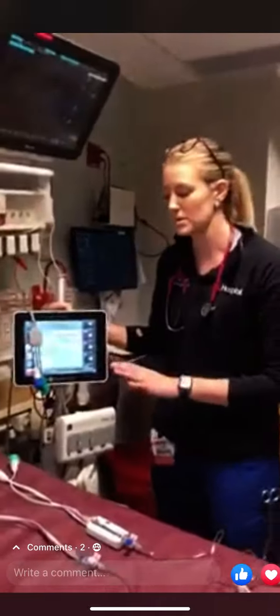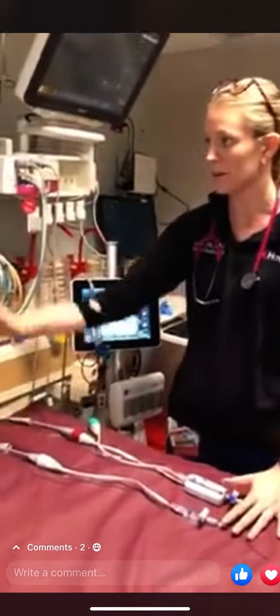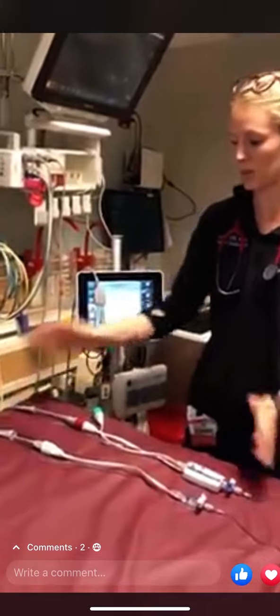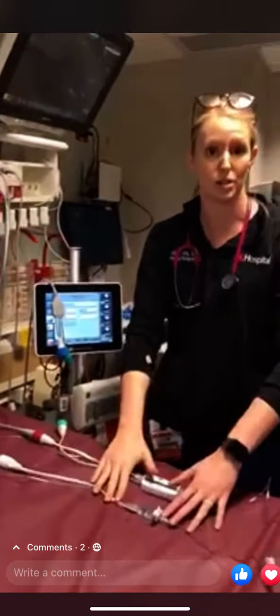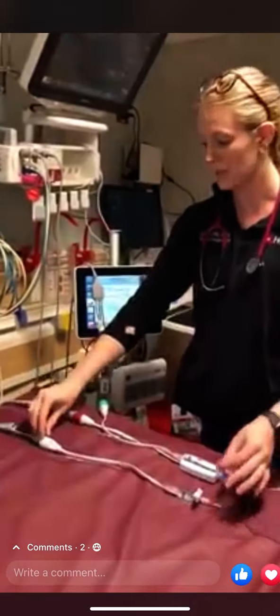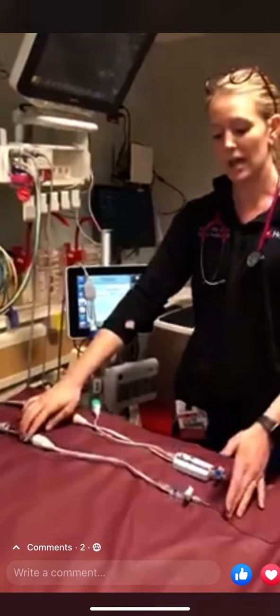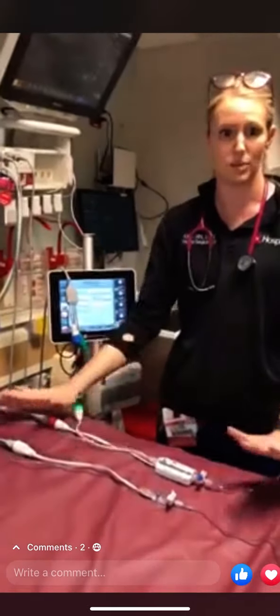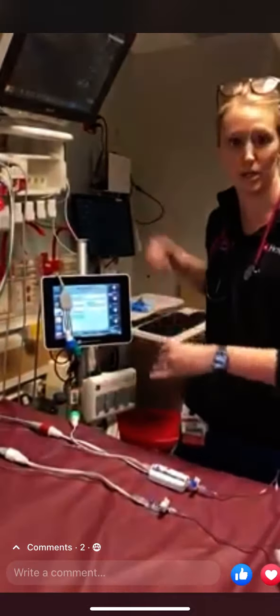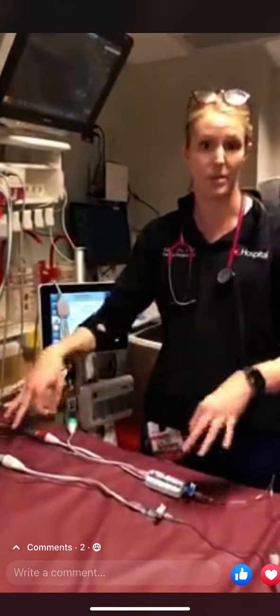Then once you've got both your cables already set up and plugged in, you're going to go ahead and start to connect your EV1000 to your cables. So I already have this set up here. We have our A-line hooked up to a pressure cable and to our monitor, and we can say hypothetically for this scenario our patient was already being monitored and has a CVP being monitored. So the patient already has a CVP hooked up, the cable's hooked up to the CVP. If this gets confusing, I think this is the easiest way to do it. So if you don't know what to do, just hook up an A-line, hook up a normal CVP, just like you regularly would, and then bring your EV1000 in, and it's really easy to do from this setup.